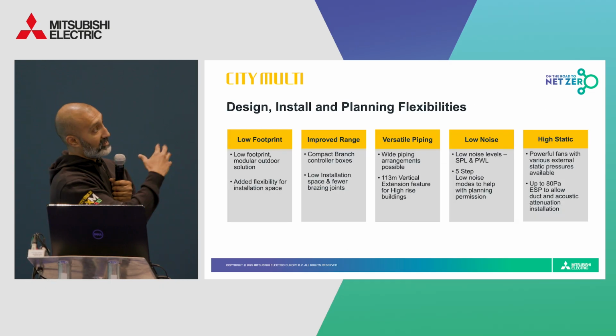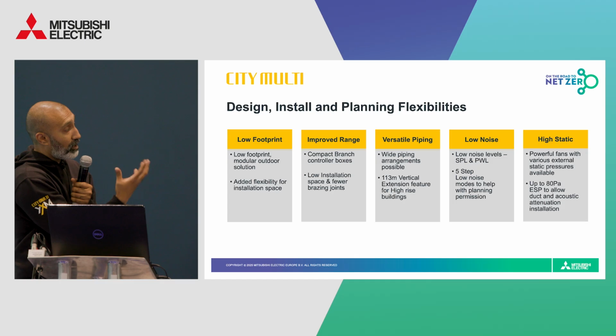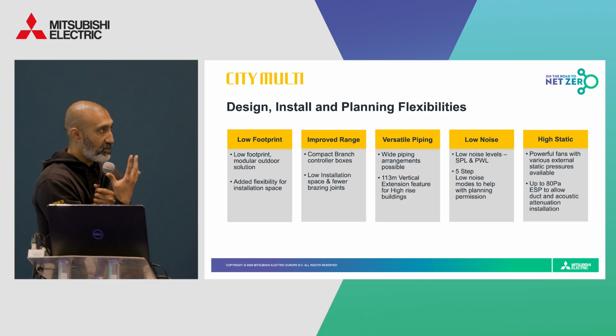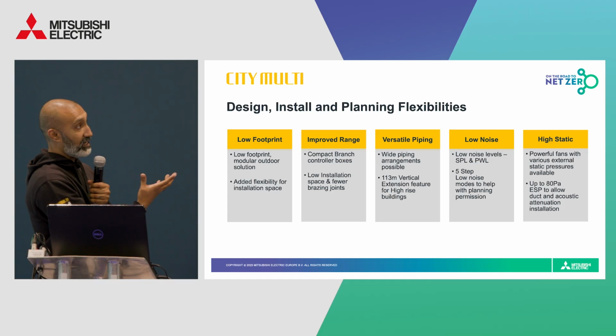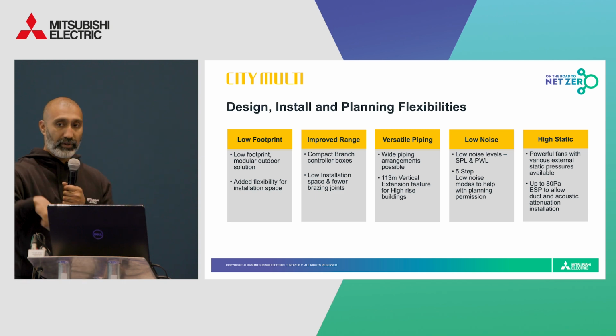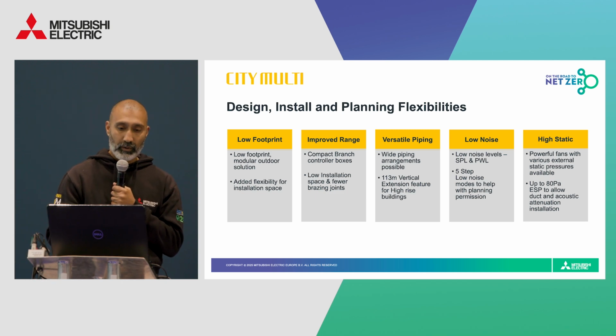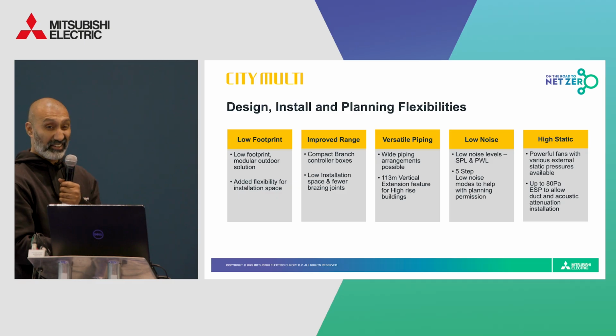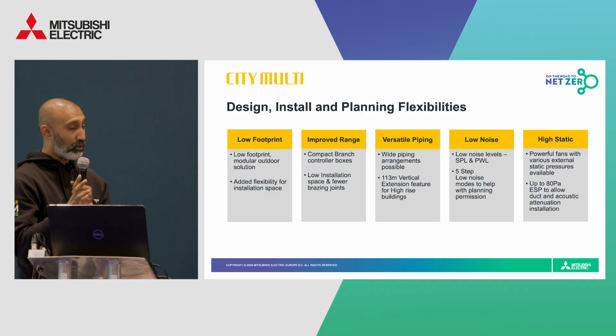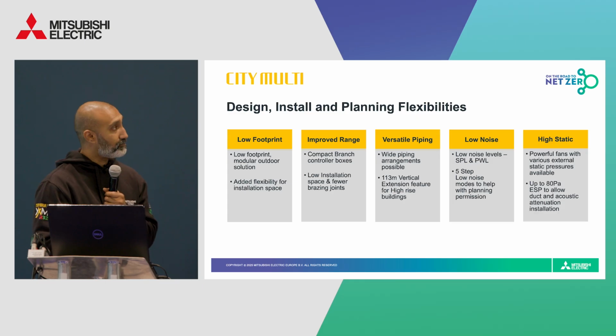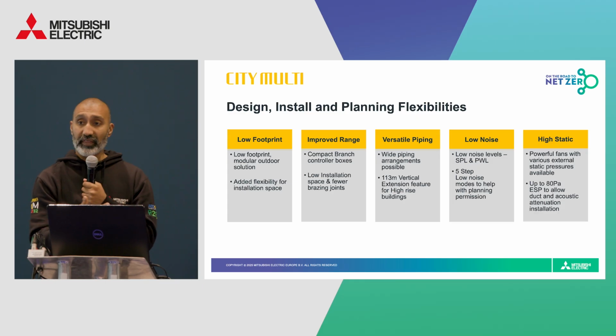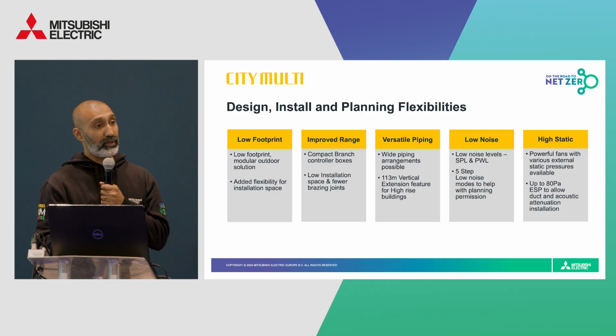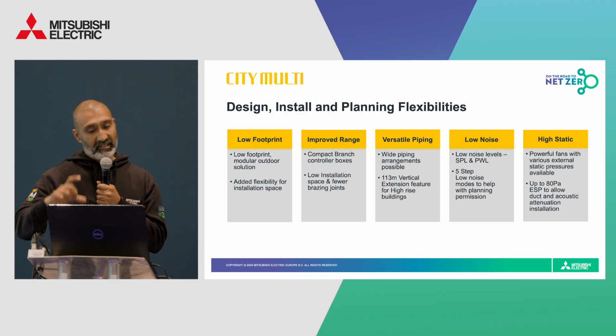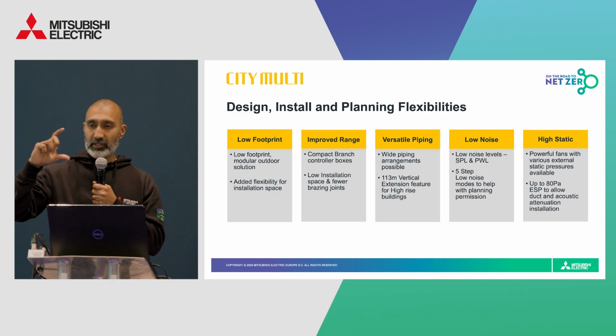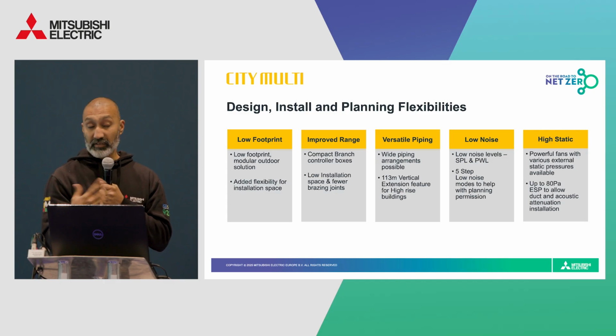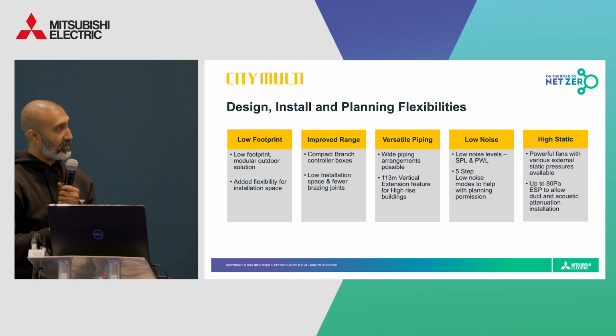So here, some of the key features. The new R32 YXM VRF solution, it will be our most flexible solution ever, particularly if we look at location flexibility. The footprint is around about 6% smaller than our current R32 competitors, and that's great considering roof space and plant room space is normally quite crammed with other mechanical equipment. Our new BC box, this will come with up to 12 ports and will have built-in shut-off valves. And the VC boxes, they'll still have that low height of 252 millimeters. So you'll still be able to fit these into really tight ceiling spaces.